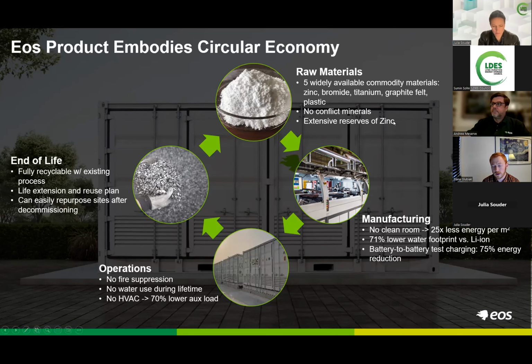The other part is our battery itself is a very thermally stable chemistry. We're a zinc-based chemistry, but we're a static sealed bipolar cell, so we're not a flow chemistry and we're not zinc air. That's a key difference between us and some historic zinc chemistry batteries. Our system is non-combustible, it's water-based, and it doesn't really generate a lot of heat when cycling. So we do not require fire suppression, we do not require HVAC, and therefore have a much simpler system design and consume a lot less energy to run our systems. Auxiliary power can be a big cost for project developers.